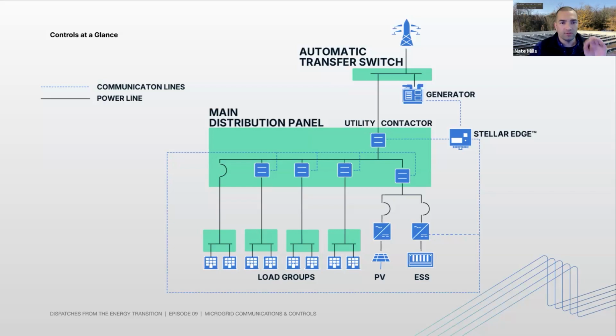As soon as the power goes out, the utility contactor will open, right? We have components that do that. That's typically not the Stellar Edge. That's typically something else, like an SEL 751 that the utility has experience with and they believe in and everybody is comfortable with. So the utility contactor will open automatically. When the battery recognizes that the utility contactor has successfully opened, it will switch from following the signals from the grid to forming its own grid by controlling voltage and frequency.